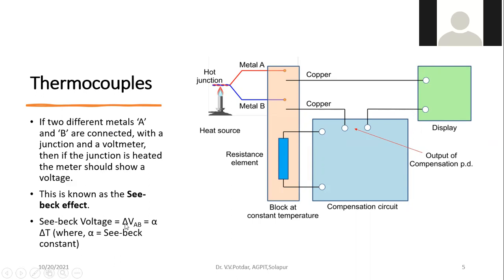Seebeck voltage, delta VAB, will be equal to alpha into delta T. So the Seebeck output voltage in case of thermocouples is proportional to delta T, where alpha is called the Seebeck coefficient or Seebeck constant. It will vary with different pairs of dissimilar metals. This is the principle of thermocouples.